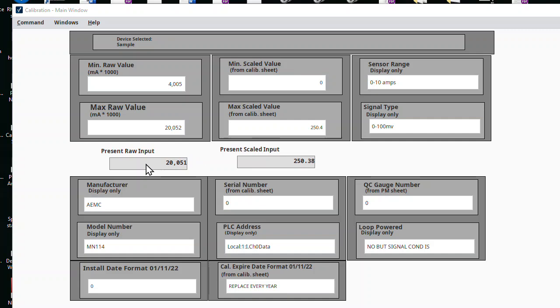Right now I'm currently injecting a 20.04 milliamp signal. Our PLC input is slightly off; it says we have a 20.052 milliamp signal. But my process meter is calibrated and I'm going through the wires, so I don't really care if the PLC is a little bit out of spec. We're just going to call this the high end because I'm injecting the correct signal. So I'm going to take 20.052 and make sure that I put that as my raw max.